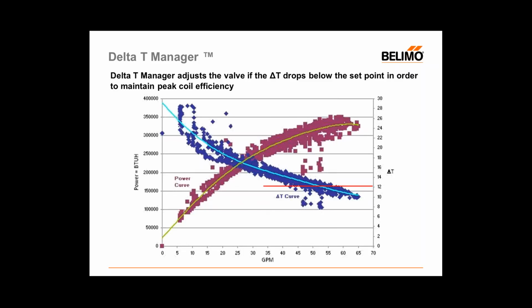But if we violate that low limit threshold, in other words, if we get below 12 degrees of delta T, and it has to be significantly enough below that we're going to register. So if you go to 11.9, the energy valve's not going to do anything. But let's say in this case we get down to about 10.5 degrees of delta T. The energy valve with Delta T Manager engaged will suspend control of the automation system, and it will start to reduce its own flow until it has satisfied the 12 degrees of Delta T.